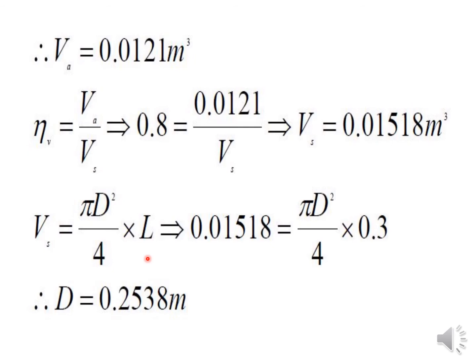The swept volume formula is Vs = (π/4) × d² × L, where d is the cylinder diameter and L is the stroke length. Here L = 0.3 m and Vs = 0.01518 m³ are known, so d is the only unknown. Solving gives d ≈ 0.2538 meters. This is the required cylinder size.